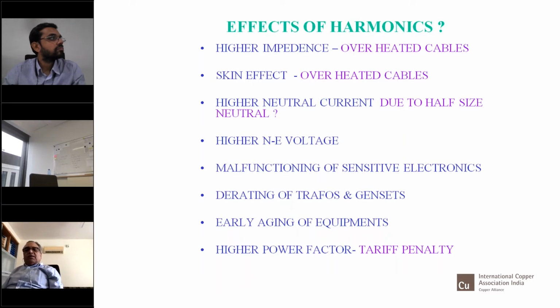So these are the problems that are faced in the industry because of harmonics. Some people are aware and are finding mitigations and solutions. Some people are just not aware and are facing problems and load drops every day. Early aging of equipment happens because of this overheating. The motors will not last long. They will have to be changed sooner than if you would have changed a motor after 10 years. Maybe in this case, in 7 years you'll have to change a motor.